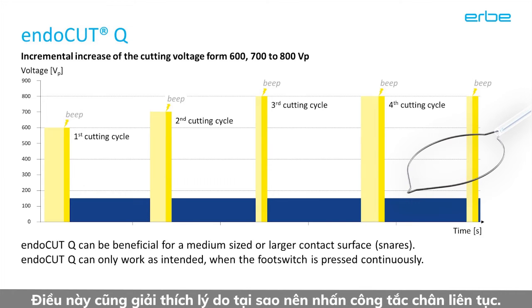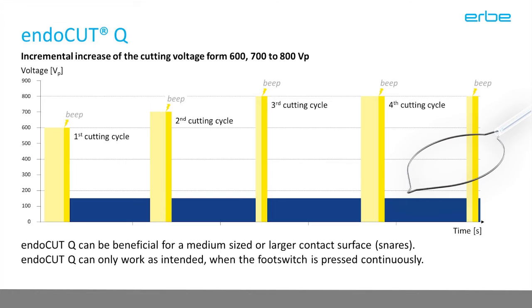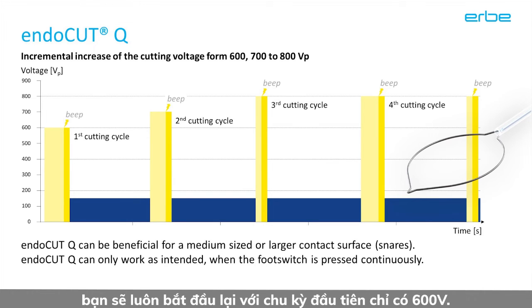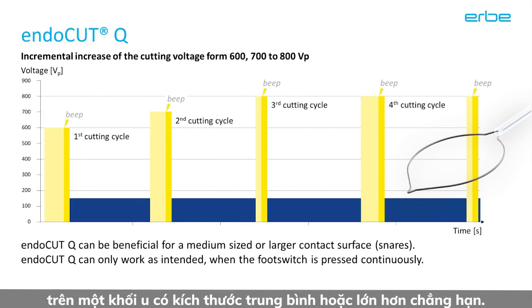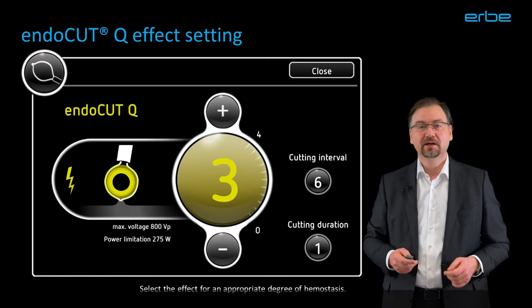This also explains why it is advisable to keep the foot switch pressed continuously. Because when you tap the foot switch, you will always start again with the first cycle that has only 600 volts. This would result in a less strong cut and would make EndoCut Q less effective. In particular when you use it with a snare on a medium or larger sized polyp, for example.